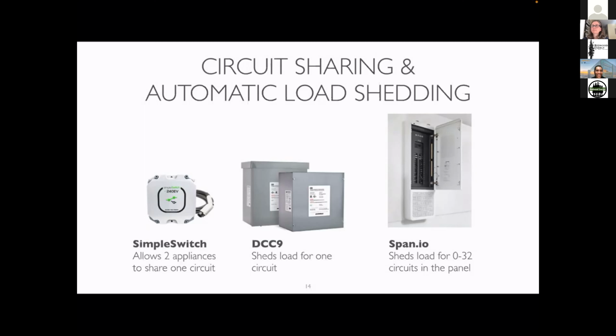On the right, we have an even more elegant solution, which is to replace your electrical panel with a smart panel. In this case, your smart panel becomes almost like an air traffic controller, so you can program all of your loads such that if you're reaching your max panel capacity, it starts to shut off different circuits in a certain order.